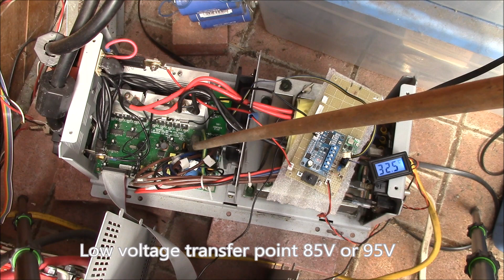The way this works is if there's power available from the grid, it takes power from the grid and runs it over here, and there are two relays on the circuit board that switch power from the grid and back out to the load. So you're powering your device from the grid, and if the grid power on this line were to fail, there's circuitry on this board that detects that and switches these relays over, starting to pull power from your batteries through the MOSFETs here.